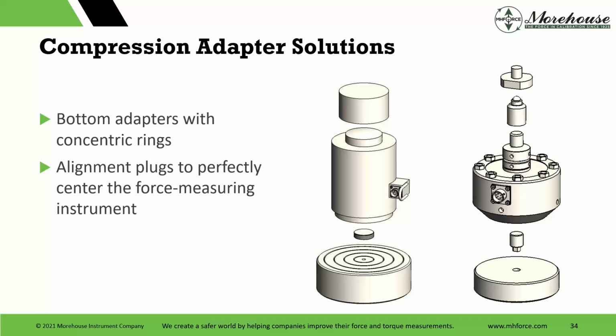Another thing, we're going to put these in the cal machine. It's still a universal calibrating machine webinar, but we're talking about how we mount the load cells and how we calibrate the load cells in the cal machine, or the dynamometers and the pins. That's what we're relating back to. So here, the one on the right would be how we mount a reference standard load cell, and the one on the left would be how you would mount your unit under test or device under test in the machine for compression. And we're recommending alignment plugs to center the instrument that should go up into the load cell.